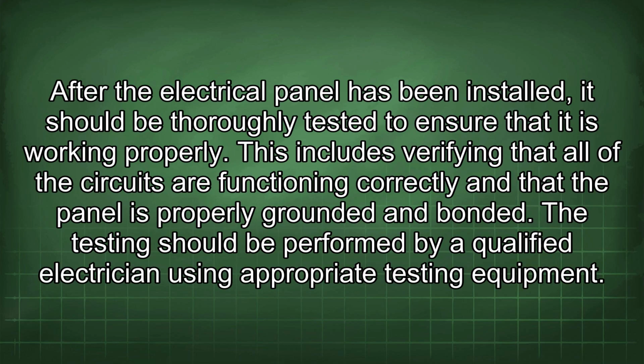After the electrical panel has been installed, it should be thoroughly tested to ensure that it is working properly. This includes verifying that all of the circuits are functioning correctly and that the panel is properly grounded and bonded. The testing should be performed by a qualified electrician using appropriate testing equipment.